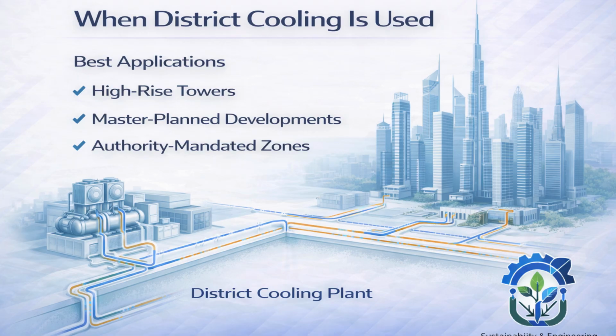Now let's understand the engineering reality of district cooling. District cooling is not optional in many projects. In many UAE zones, the authority mandates district cooling and mandates chilled water connection as compulsory. As engineers, our role is not to debate the system but to design ETS rooms correctly, comply with utility standards, and ensure proper interface between building systems and utility supply.